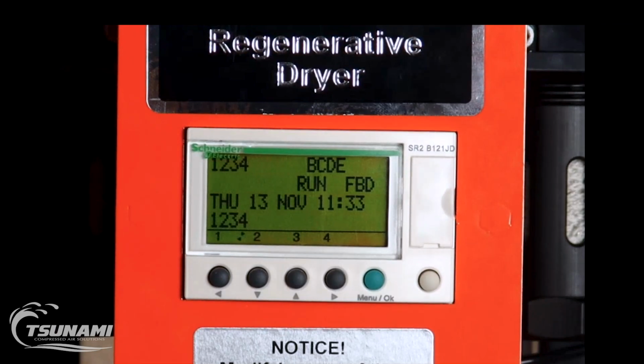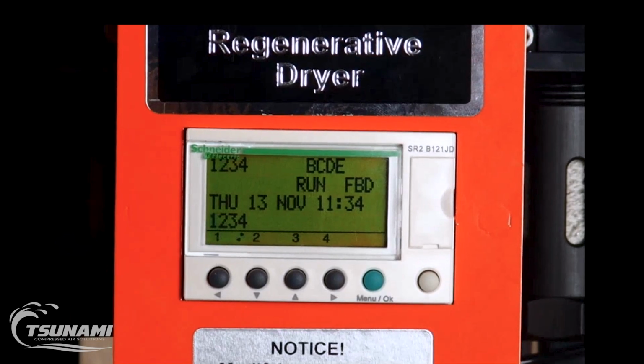Now these PLCs are configured to allow a lot of versatility. So we can receive multiple inputs. We might have 2 compressors. We might have this dryer between 2 pieces of equipment. And when those pieces of equipment are going to use compressed air for some valve actuation or whatever it is, we're able to utilize some dry contact or some signal from that equipment. We can use up to 2 inputs coming into this for this programming. So when that's the case, you'll see that we now have multiple inputs. Configured the way that we currently have it, with block 4 in the parameters reading 1 and block 5 being at 0, whenever we receive an input signal from one of the 2 contacts, the program runs. If we take that signal away, the program will stop.